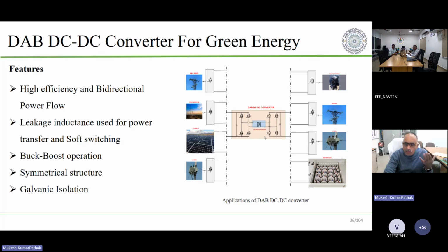For example, the converters we were using earlier, few years back or 10, 20 years back, used IGBTs, with power handling capabilities of only a few hundred kilowatts or a few kilowatts. An efficiency of 90% at 10 kilowatts is not posing any challenge, because 10% power loss means you lose 1 kilowatt. Handling this dissipation is not a big problem, and efficiency-wise you are only losing 1 kilowatt.